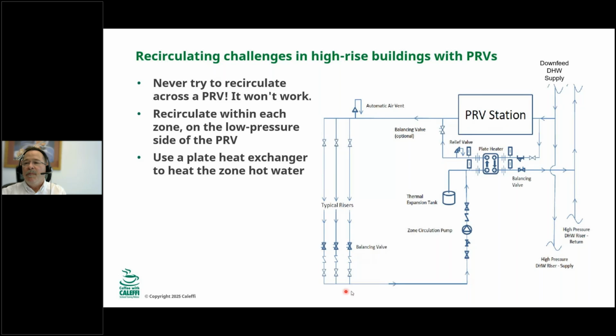But you can put in a plate heat exchanger right here. Look at the piping before you go to the PRV: pull off your high pressure, run it through a plate heat exchanger, put a balancing valve in there, and then go back to your high pressure. So everything over here is in the high pressure system. Then on the other side of this plate heat exchanger, you're going to have your zone circulation pump, pumping that water through the plate heat exchanger and serving all of your risers or your secondary circuits here on the low pressure side of the PRV. Okay, that's another way to do it.